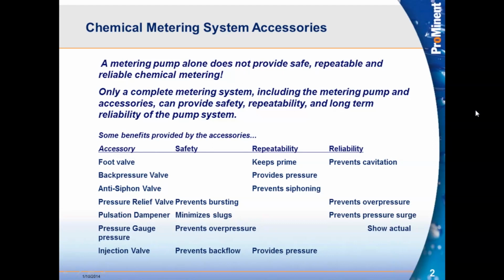A pulsation dampener, we'll talk about that early on in this presentation. It's very important to us, particularly as the volume per stroke we're dealing with gets larger, it becomes more and more important, and we'll see why. The gauge. Setting those back pressure and relief valves, we can't guess at that. We want to know what those pressures are. Gauge, and we always include an isolator with that gauge. Many times the chemical that we're pumping isn't compatible with the material that the gauge is made out of, whether that is stainless steel or maybe nickel-plated brass or something like that. That can go away very easily if we don't separate the chemical from being in contact with that gauge. So that gauge isolator is very important as well.